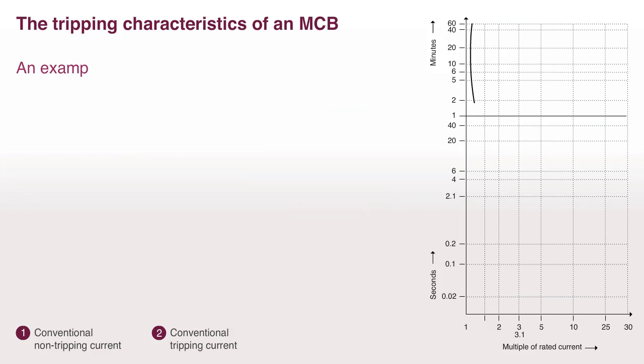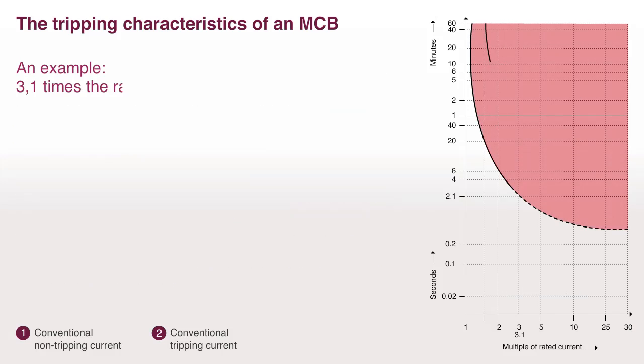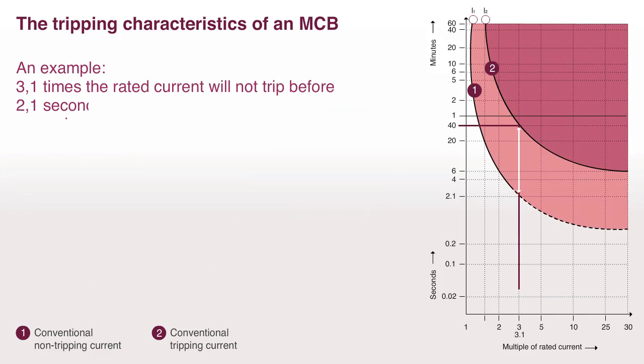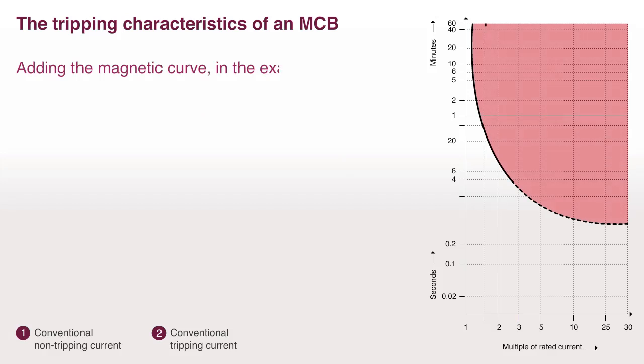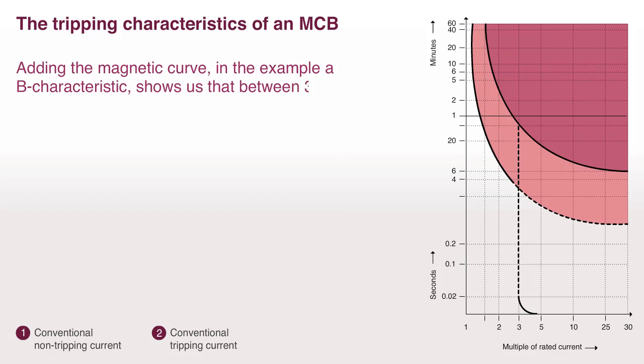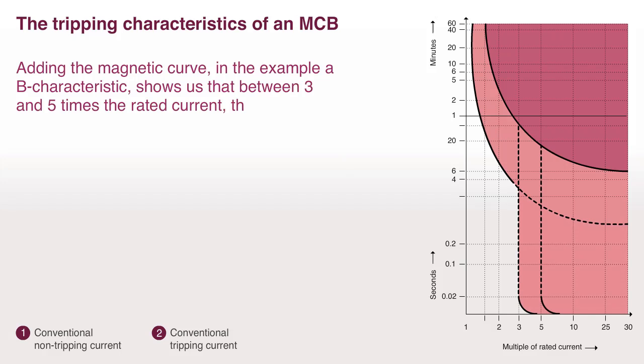An example: 3.1 times the rated current will not trip before 2.1 seconds, and the latest trip will occur after 40 seconds. Adding the magnetic curve, in the example of B characteristic, shows us that between 3 and 5 times the rated current, the magnetic coil will trip the MCB.